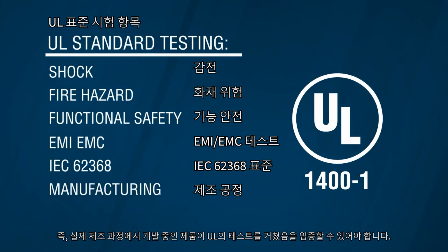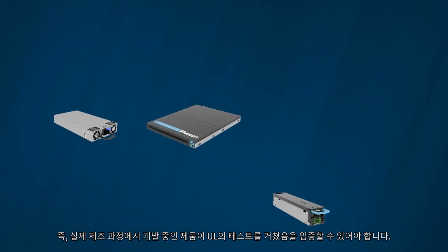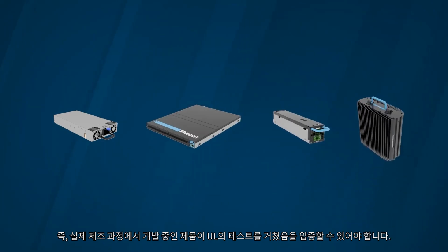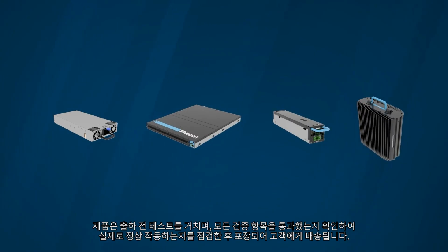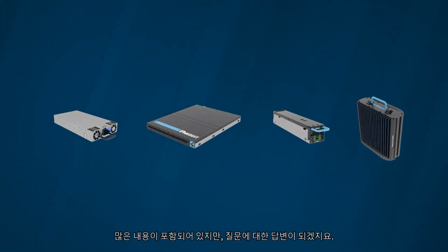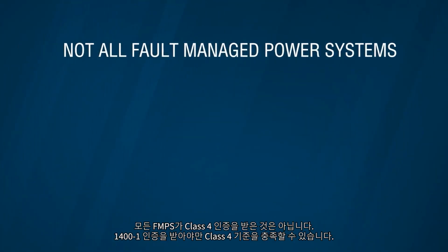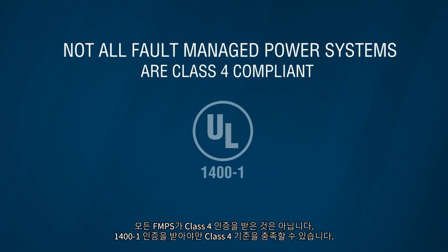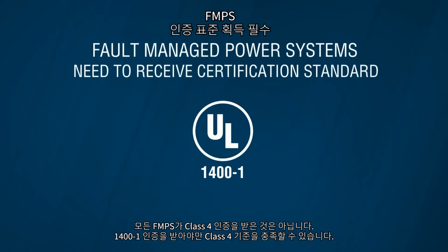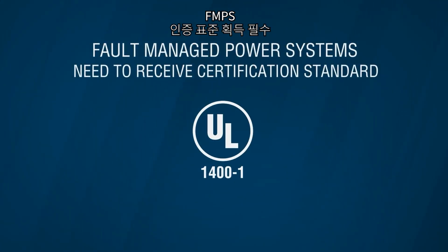So you actually have to prove that the product you're developing and have been tested by UL, when it's actually being manufactured, goes through an end-of-line test that rolls through all these tests and makes sure that it actually functions before it's packaged up and shipped to the customer. So there's a lot there, and to re-answer that question, no, not all fault managed power systems are Class 4 compliant. They have to get the 1400-1 certification.